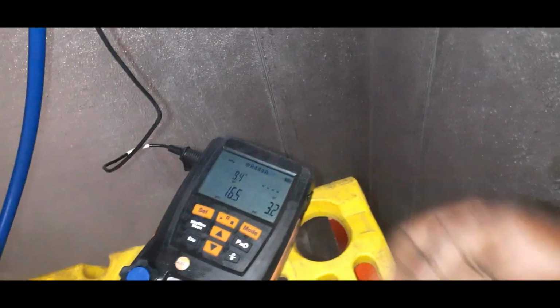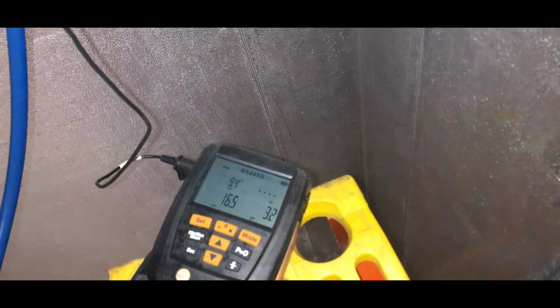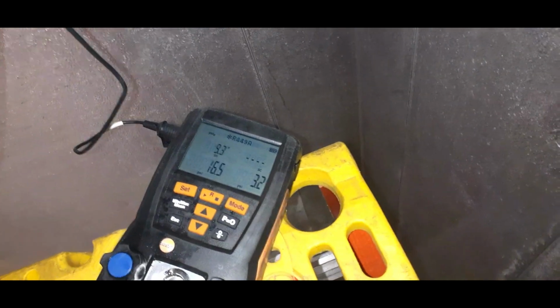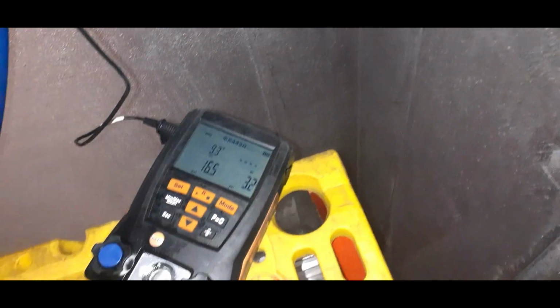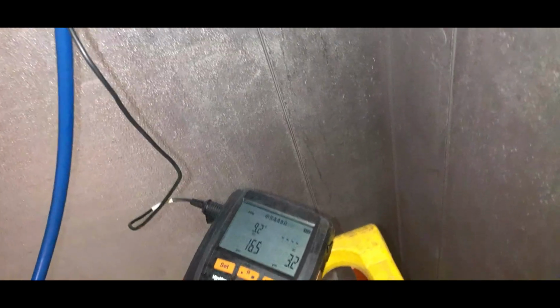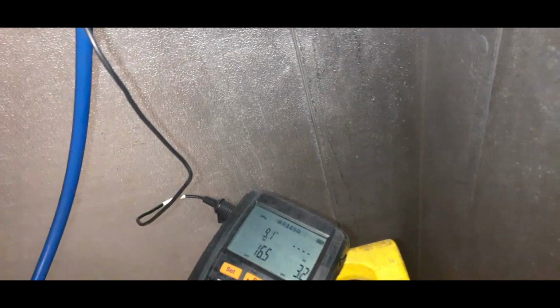So basically, when you're looking at your pressure gauges, pressure controls the temperature, and temperature controls the pressure. So whatever your pressure converts to temperature-wise, that's your coil temperature, like the inside of this coil. And basically, these units are designed with a 10-degree TD. So that's basically your coil temperature minus the return air temperature. And the return is the air that's entering the backside of the evaporator. So return air minus the coil temperature. You should be, like I said, 10 degrees.